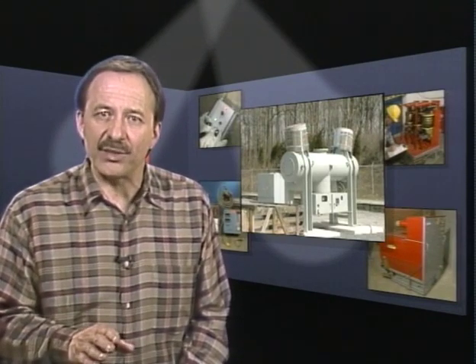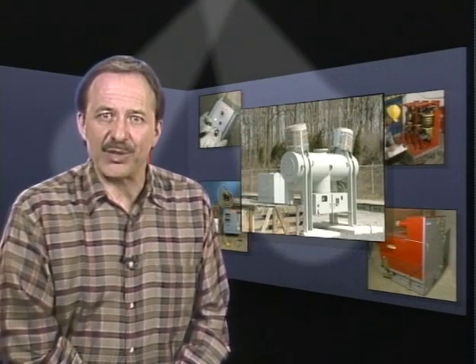But an acceptance inspection doesn't ensure that the breaker is ready to be put in service. It still needs to be properly installed, re-inspected, and tested. In the next part of this program, we'll look at circuit breaker installation. But for now, read the material in your text on receiving and answer the questions provided.